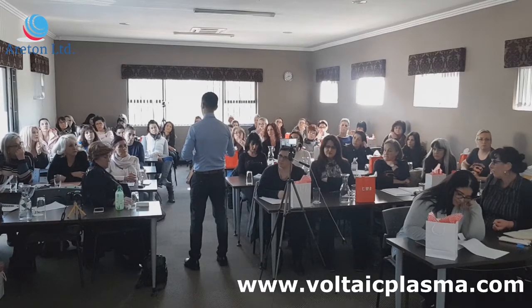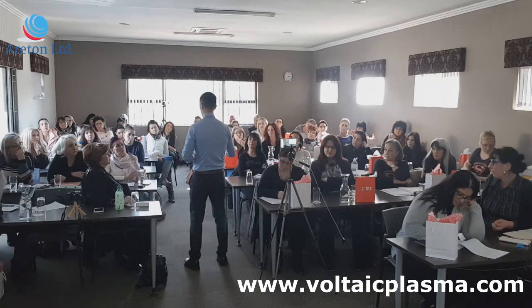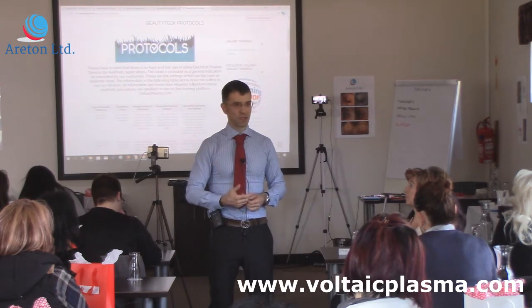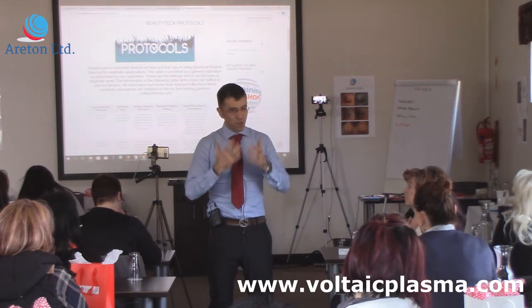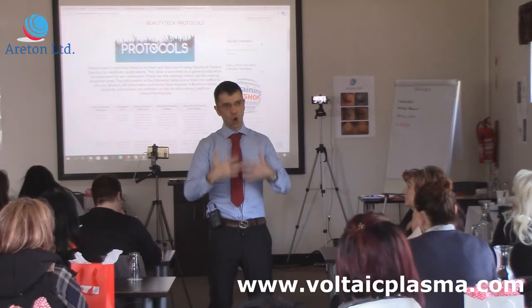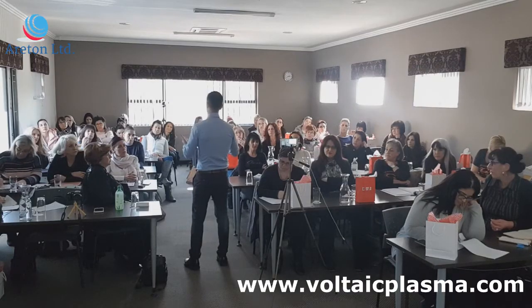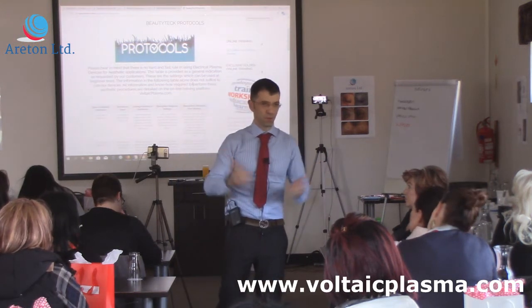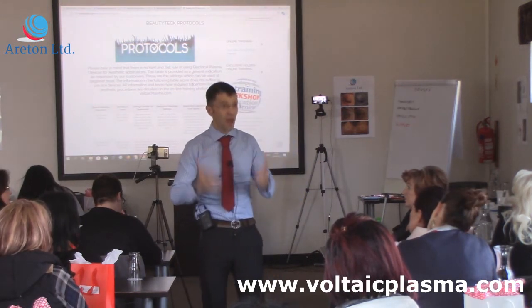At the moment, one of the most important points of how you use the device is the duration of the arc. This is the problem that we're sorting out next year with a new device. It's not as if you've got 3 power levels or 1 power level. Oh, it's everything, I'll do everything with 1. You can. You actually can.